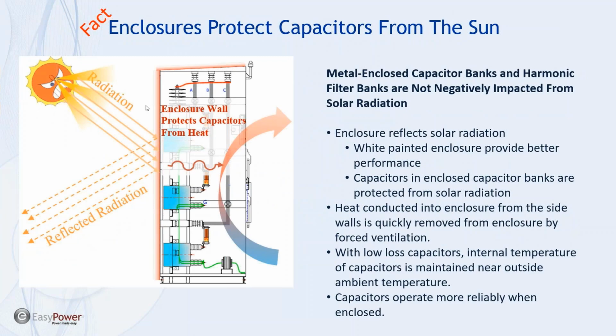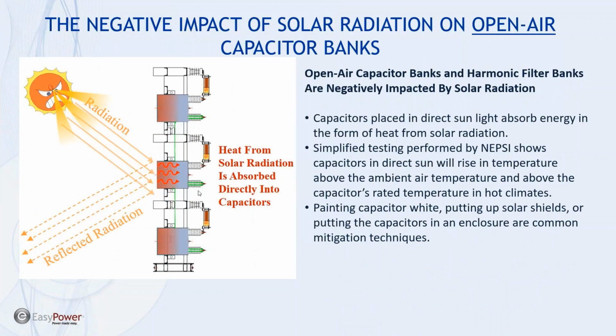When the sun is hitting an enclosure, it reflects the sun away. The sun is not hitting the capacitors, where the capacitors can absorb heat. So therefore the capacitors run cooler. And then we force air through the enclosure. So we're isolating the sun away from the capacitors, and we're providing ventilation. Capacitors themselves only have a loss value of 0.05 watts per kVAR. So they in themselves have a very low watt rating for losses.